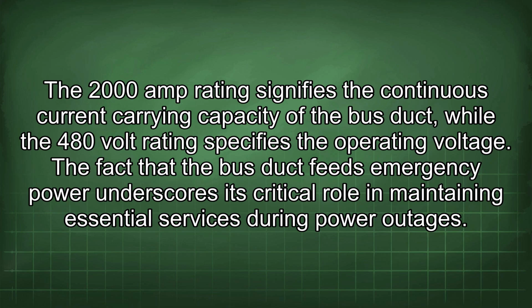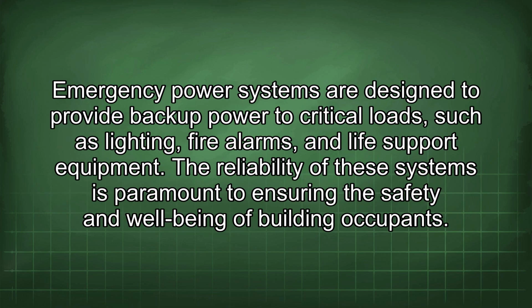The fact that the bus duct feeds emergency power underscores its critical role in maintaining essential services during power outages. Emergency power systems are designed to provide backup power to critical loads such as lighting, fire alarms, and life support equipment. The reliability of these systems is paramount to ensuring the safety and well-being of building occupants.